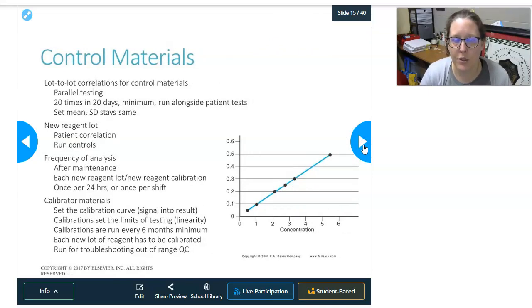So again, you need to do a lot-to-lot correlation for the control materials. And this is called parallel testing. Just like we talk about parallel testing between an old analyzer and a new analyzer, you do parallel testing with the current control material you're on and the new control material that you're about to switch to. At the bare minimum, they need to be run 20 times in 20 days. This is not run them 20 times the same day. This is run them at least once a day for 20 days. That's the bare minimum. And you run it alongside your patient tests while you still have your old lot number of controls running, making sure that your analyzer is functioning properly. And then you set the mean, and the standard deviations tend to usually stay the same. And then you can go and start running with it.